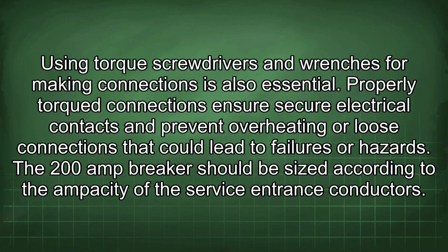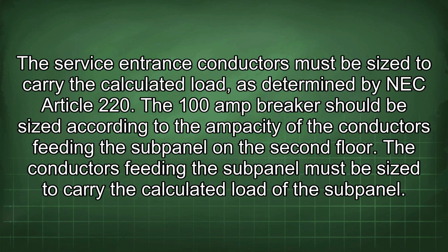Using torque screwdrivers and wrenches for making connections is also essential. Properly torqued connections ensure secure electrical contacts and prevent overheating or loose connections that could lead to failures or hazards. The 200 amp breaker should be sized according to the ampacity of the service entrance conductors. The service entrance conductors must be sized to carry the calculated load, as determined by NEC Article 220.